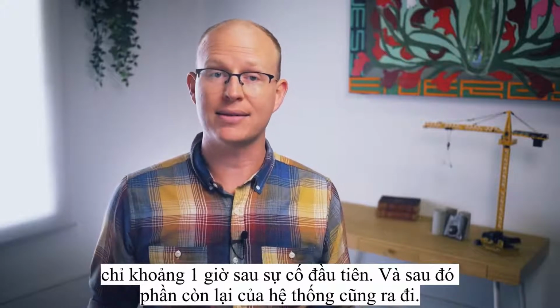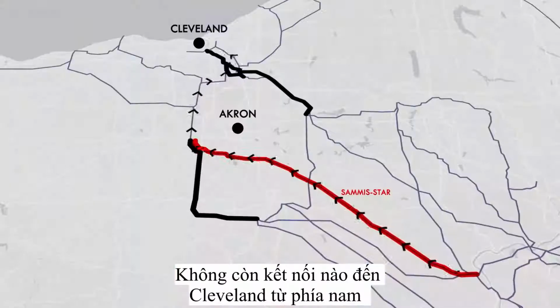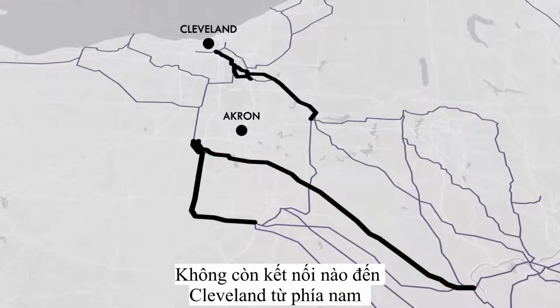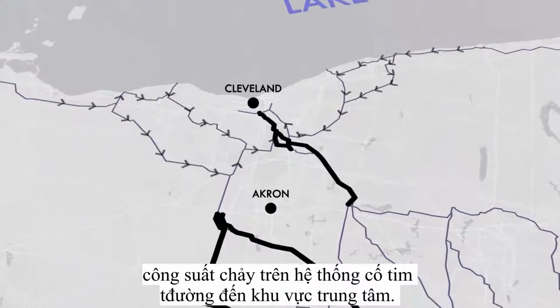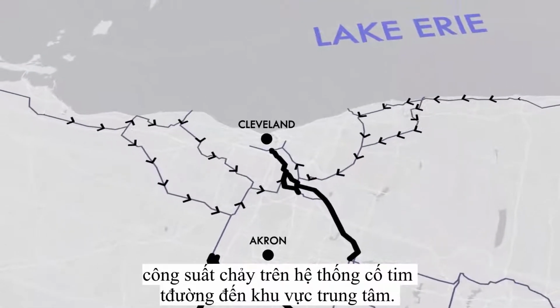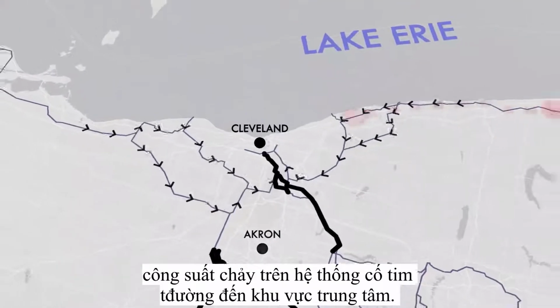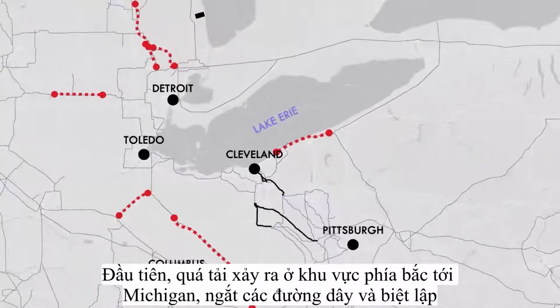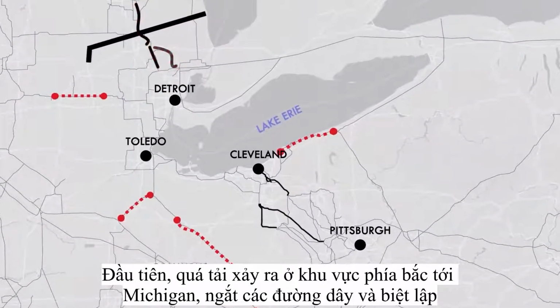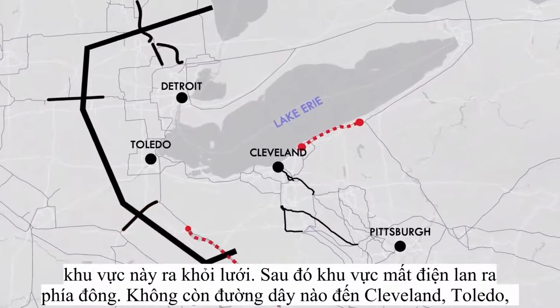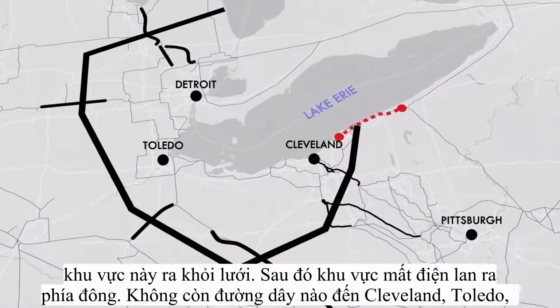After that, the rest of the system unraveled. With no remaining connections to the Cleveland area from the south, bulk power coursing through the grid tried to find a new path into this urban center. First, overloads progressed northward into Michigan, tripping lines and further separating areas of the grid. Then the area was cut off to the east.